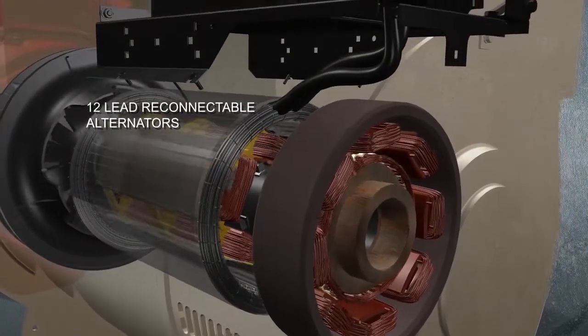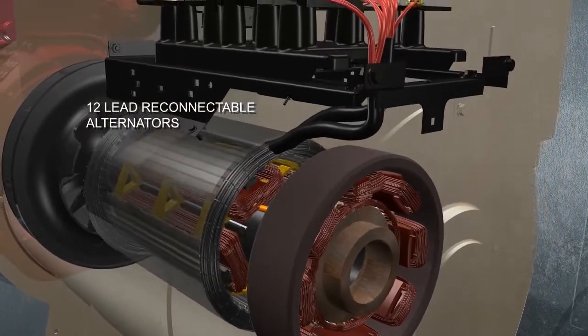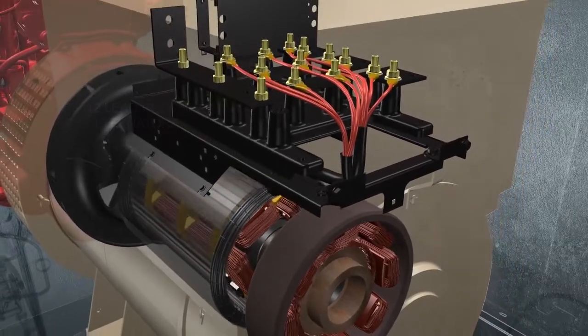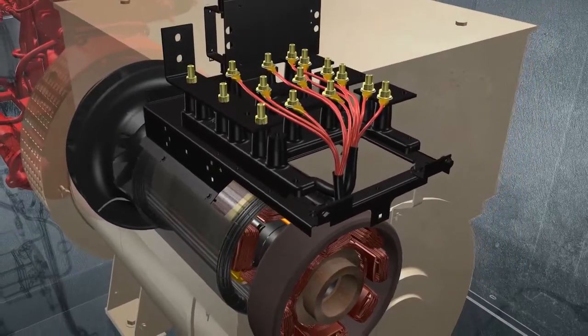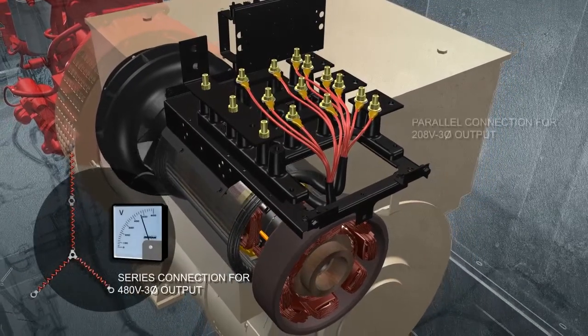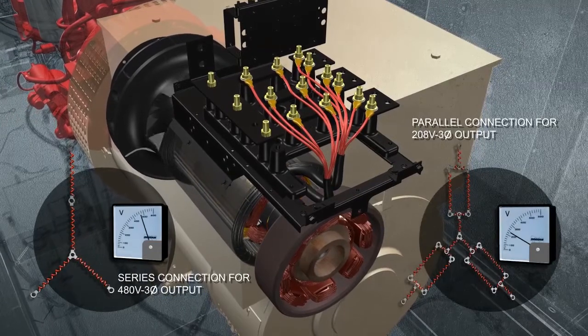Doosan Mobile Generators also include alternators with six coils wound into the stator. This provides three voltage sources or phases. Because each phase combines two coils of wire, the sources can be connected in series for high voltage applications or in parallel for low voltage needs.